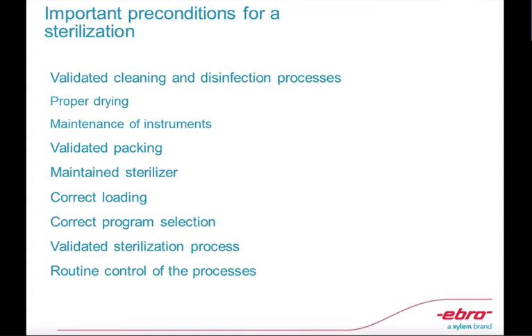These are the important preconditions for sterilization. As we mentioned, cleaning and disinfection processes must be validated, because it is hardly possible for an object or material that is not clean to be sterilized. Then proper drying, maintenance of instruments, the packaging, and a maintained sterilizer — meaning a properly working autoclave — the correct loading, the correct program selection, and validated sterilization and routine control processes. These are your checklists for sterilization procedures.